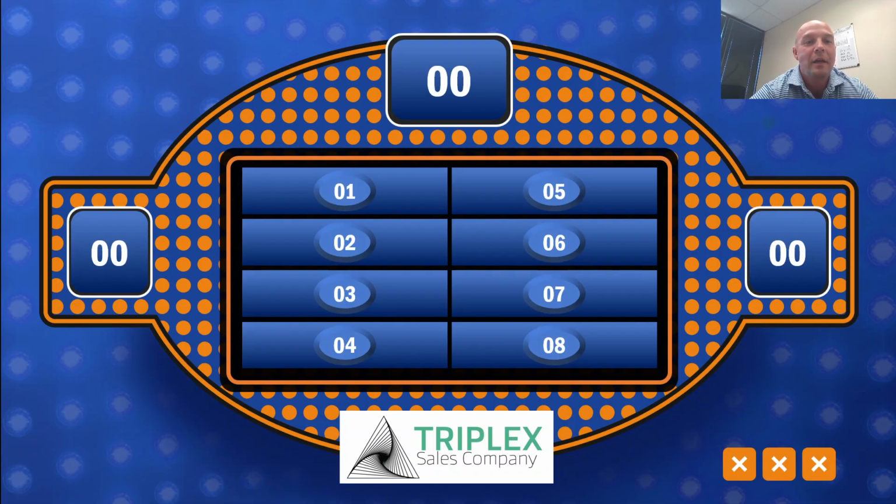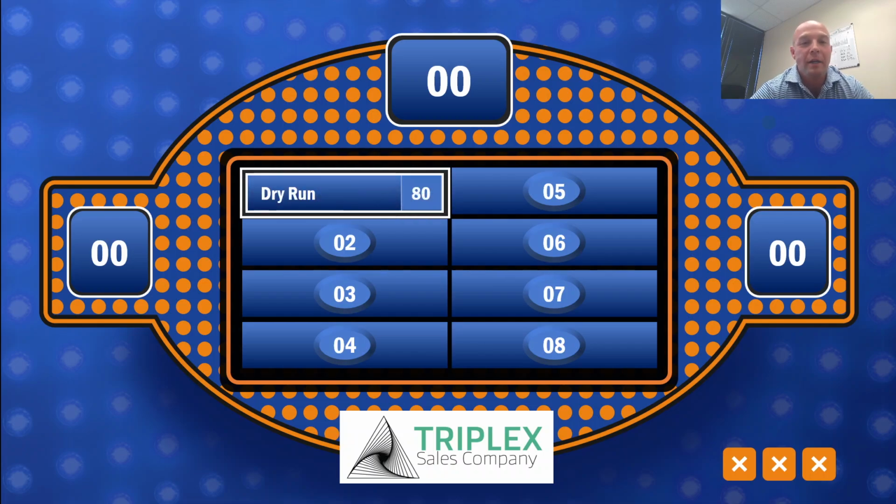life. First, we have dry run. So running dry is probably the most common reason why we see a PD pump run dry. If we're running a single seal, either a single O-ring or a single mechanical seal, we absolutely cannot run that dry. The way that these seals work is that they need a lubricating fluid to help dissipate heat. In the absence of that, we're going to see an excessive amount of friction build up. Seals are going to rip apart, fail, and product's going to leak.